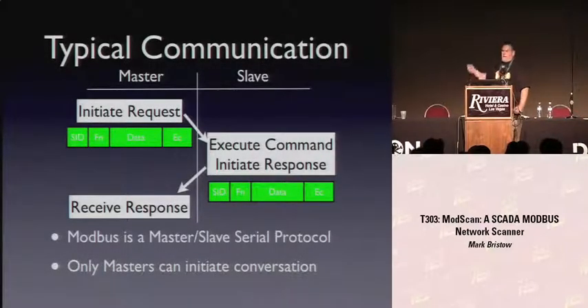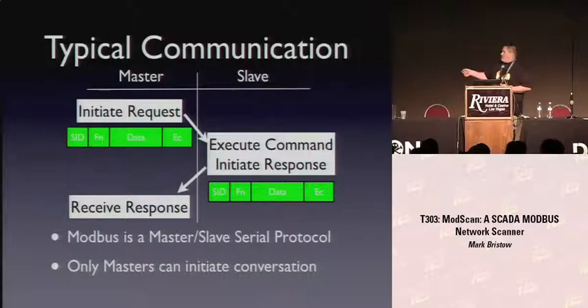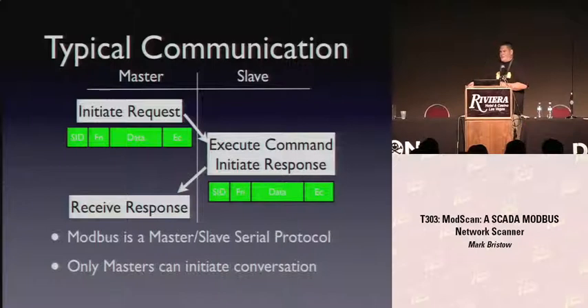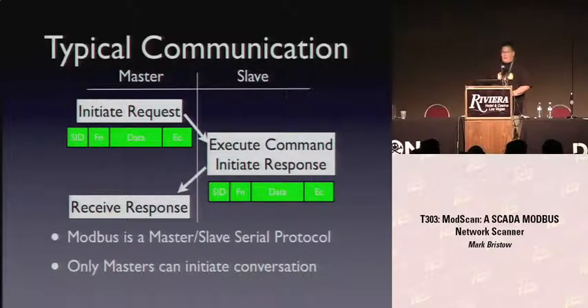Now let's talk about communication flow. It's really simple. You've got a master and a slave. Masters are the only ones that can start communications - slaves cannot under any circumstances, at least in the spec, though some vendors have added that functionality. Basically a master sends a request out to a slave, the slave does something, and the slave responds. Pretty simple.